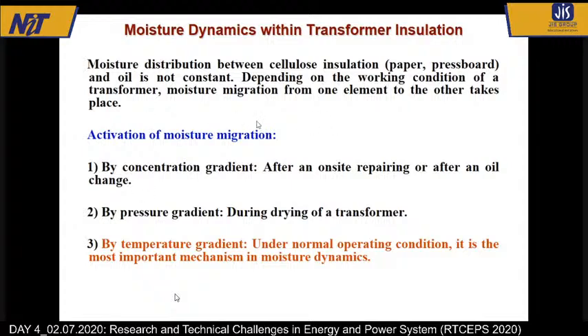But generally, this moisture migration, meaning movement of moisture within the transformer, can happen because of concentration gradient. Concentration gradient happens when we generally replace the oil, then suddenly the new oil has less moisture than what's already inside, which already has moisture. So concentration of moisture in paper is higher than in oil, and moisture moves from higher concentration to lower concentration.